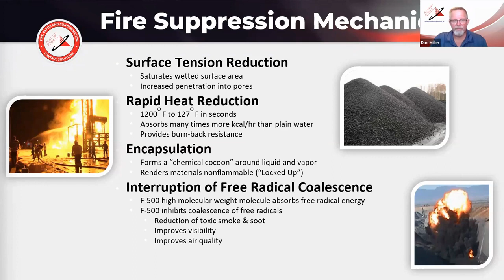So if we look at the three-agent comparison between a wetting agent under NFPA 18, a foam under NFPA 11, or an encapsulator agent under NFPA 18A, we see some differences that help the encapsulator have a foothold as a better agent than the other two typically. Number one, a wetting agent has surface tension reduction, which helps it spread and penetrate, and heat reduction because of the smaller water droplets, the more surface area, but it does create more steam than plain water alone.